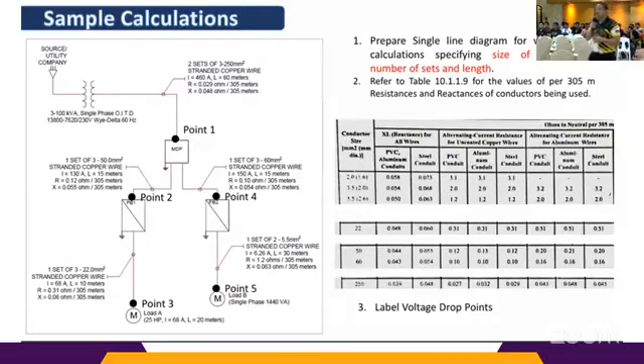Okay. So the sample calculation is coming from the utility company. We have a 3 100 kVA single phase oil immersed distribution transformer, 13.8 kV to 230 volts, Y delta, 60 hertz. We have 2 sets of 250 mm square stranded copper wire. Then we have a current of 460 amperes. The length is 80 meters. Our resistance coming from the PEC is 0.029 ohm per 305 meters, and the reactance is 0.048 ohm per 305 meters.